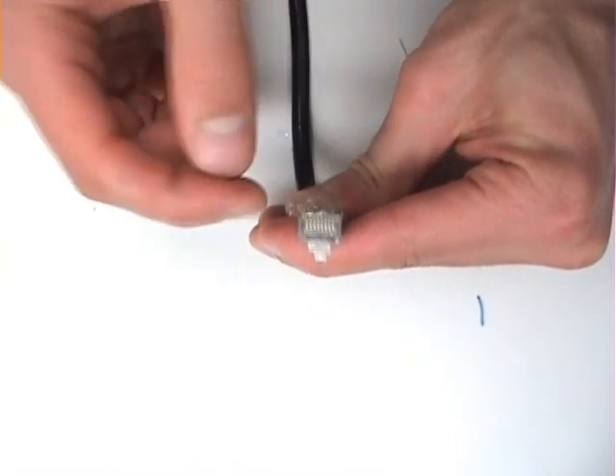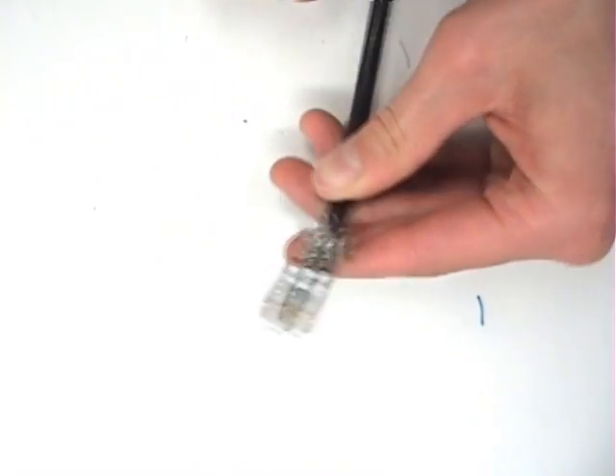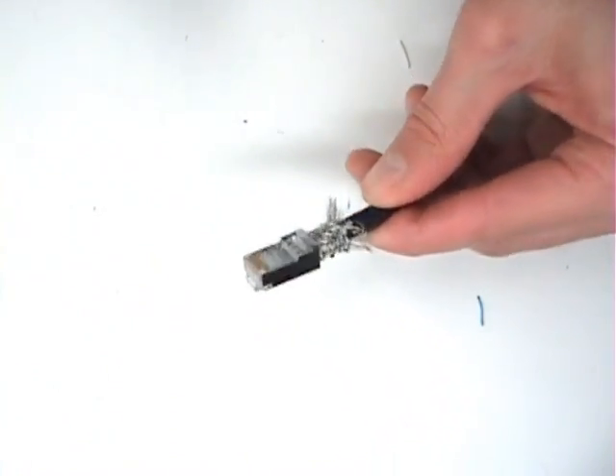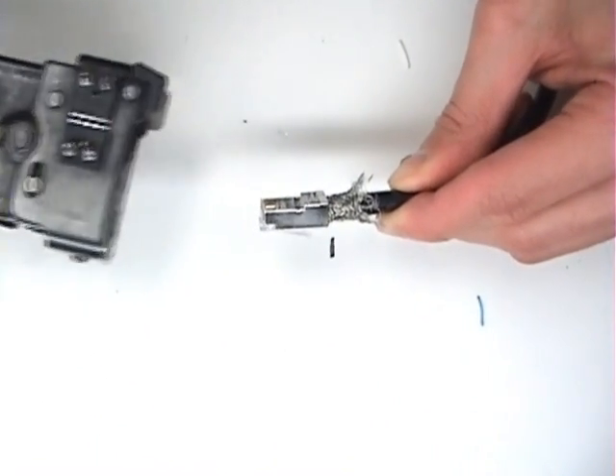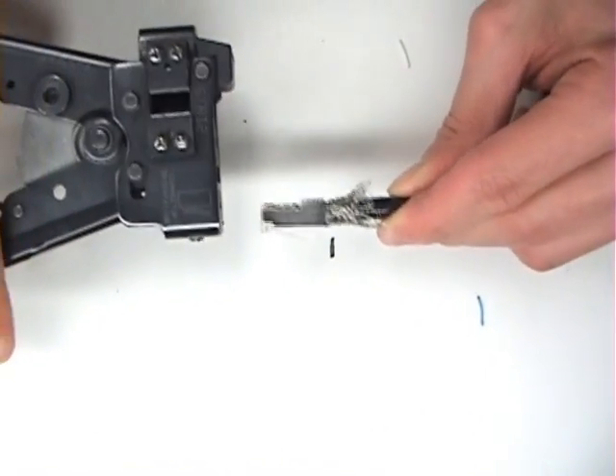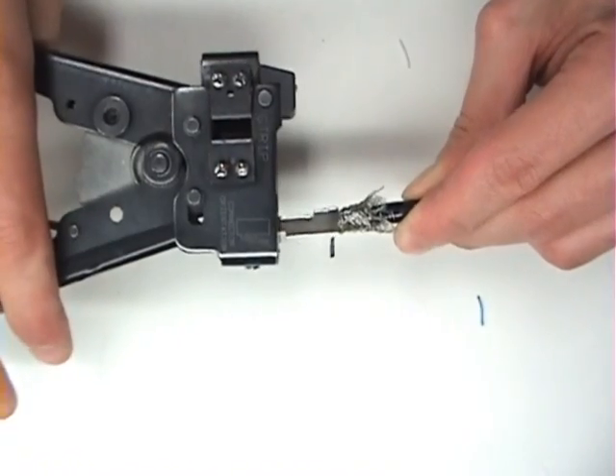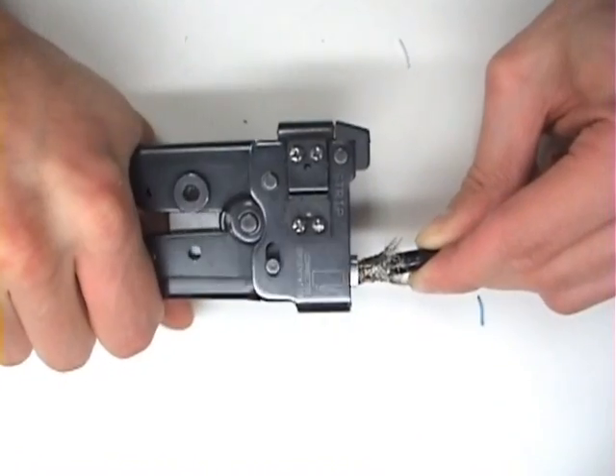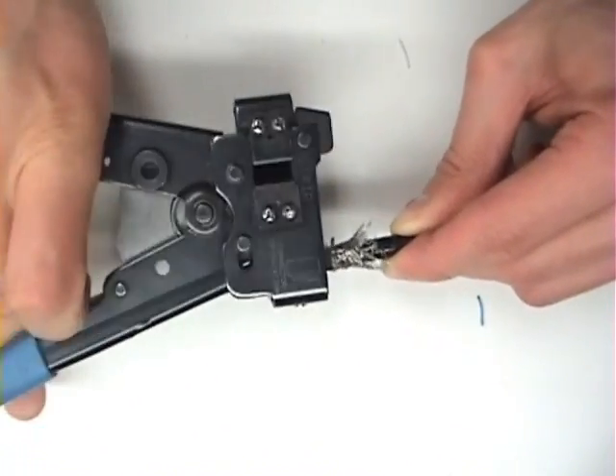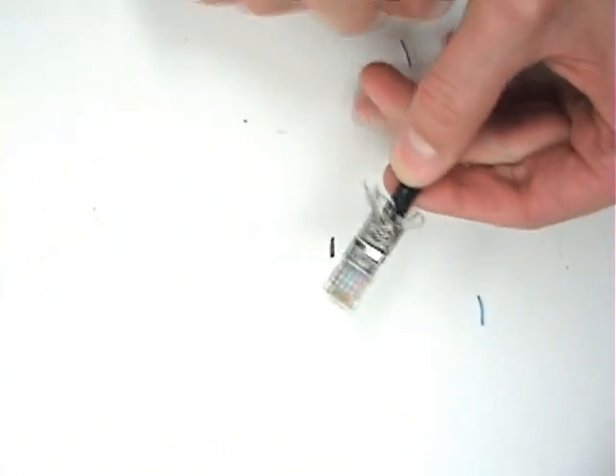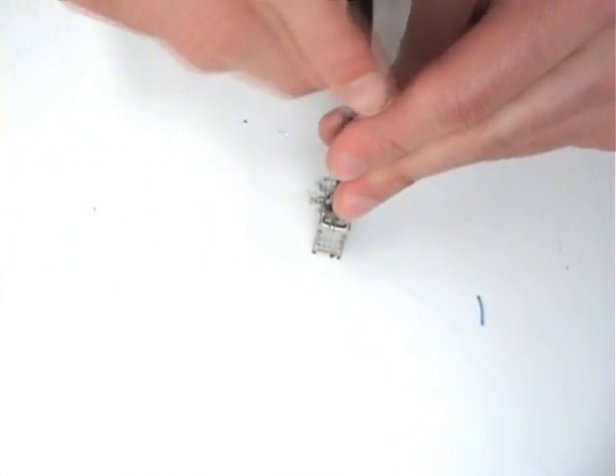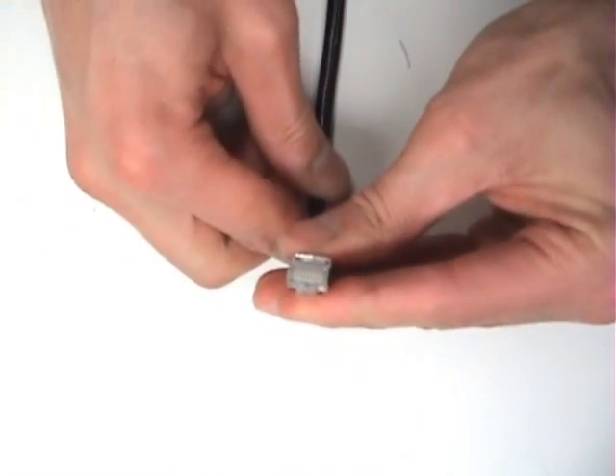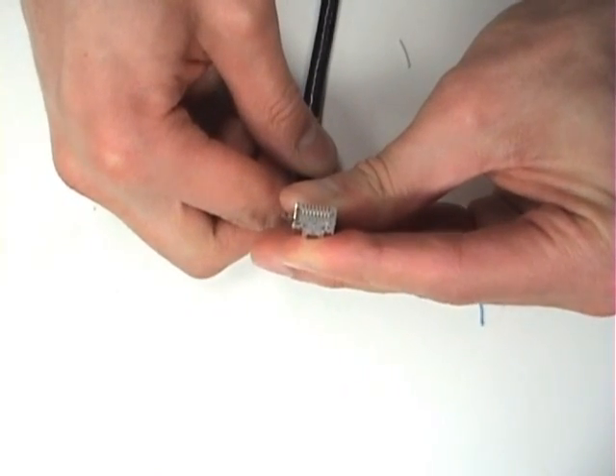Double check you can see your copper tips. And make your crimp. After crimping, ensure that all the teeth have been crimped down. And ensure that you can see all your copper tips.